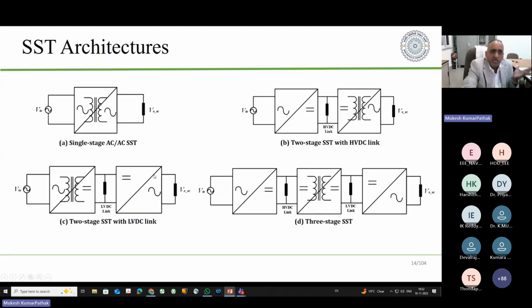So the next question is which architecture or topology to use: this one, or the third or fourth. We will have to see the application. In case there is no application of DC supply, there is no DC load or DC input, then this is good. In case there is a DC requirement, either a DC generating station or a DC load of high voltage rating, this would be good. And if it is a low voltage DC link, this would be good. This will be the best option. And if you want to integrate both high voltage and low voltage DC, this would be the best architecture.